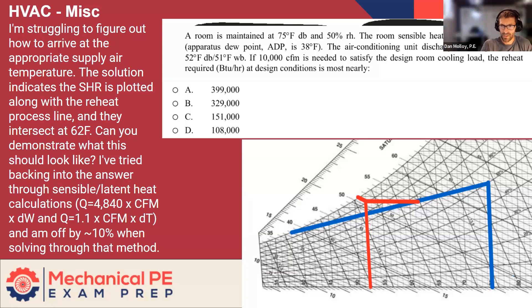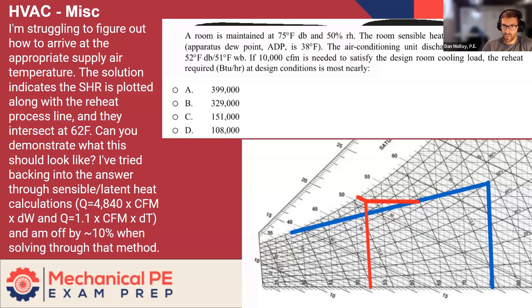So let's read the question. A room is maintained at 75 dry bulb and 50% RH. The room sensible heat ratio is 0.66, which corresponds to an apparatus dew point, or ADP, of 38. The air conditioning unit discharge air temperature is 52 dry bulb, 51 wet bulb. If 10,000 CFM is needed to satisfy the design room cooling load, the reheat required at design conditions is most nearly what?